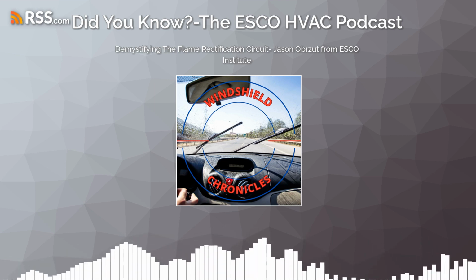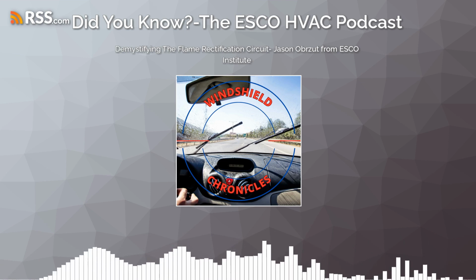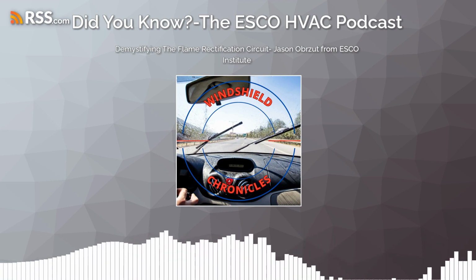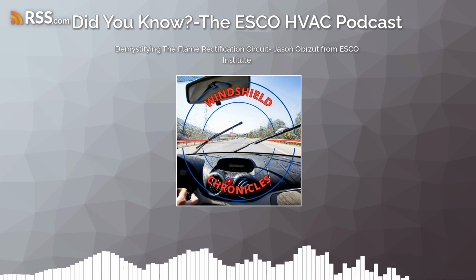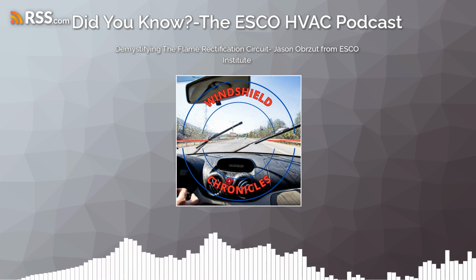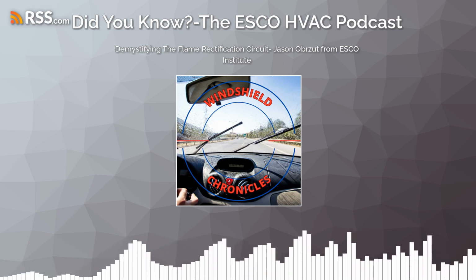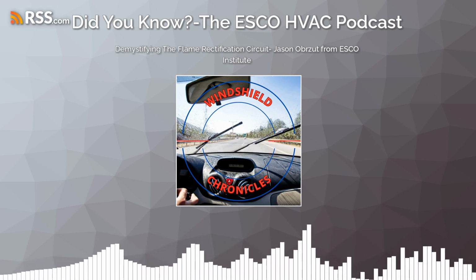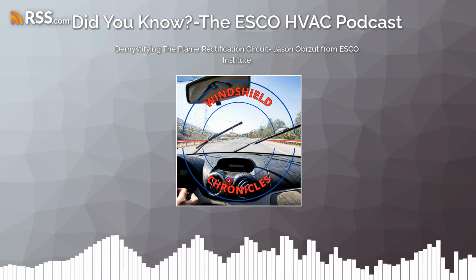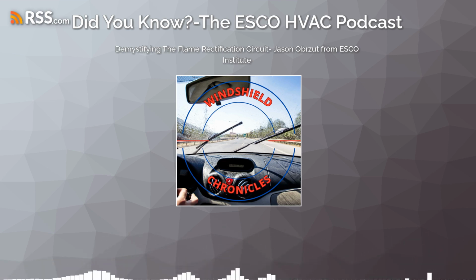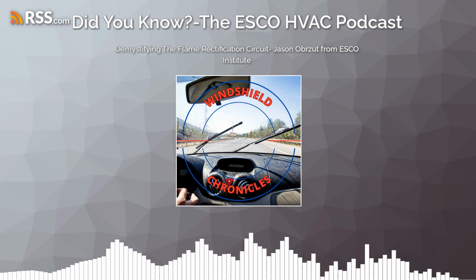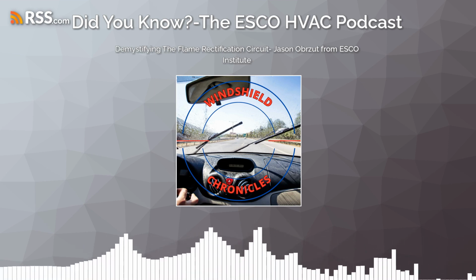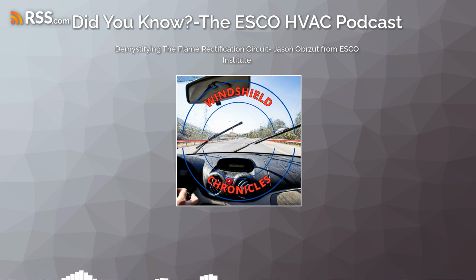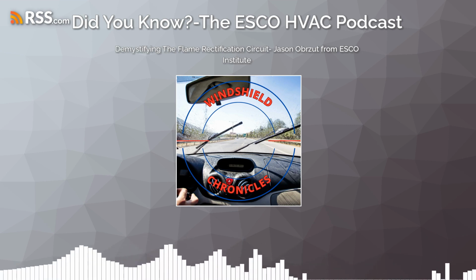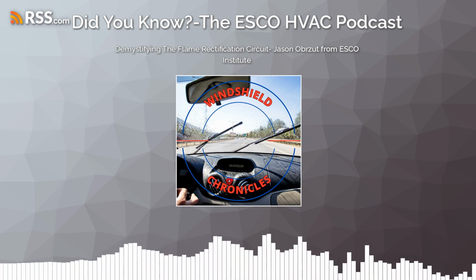So what this can do, it can tell you not just about your thermocouple or your thermopile, but actually the quality of the flame being used to heat it. Yeah. If you have a brand new thermopile or thermocouple and you're getting these low readings, it may be the issue is the quality of that pilot flame. It might be a weak flame. It might be dirty. Right. So there's a lot of things you can do with it. That's super important in this conversation. So what we're saying is that with a thermocouple and a thermopile, heat is absolutely crucial to be able to use this safety device. Right? The heat is the function of generation for voltage. That's what I was taught.